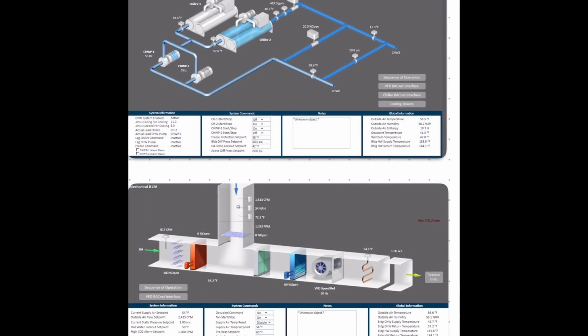Alright, so I put these 2 pictures together so you can have a better idea how the water cycle runs from the air handler to the chiller, or from the chiller to the air handler. You return from the air handler, goes here, then it goes to your pump first, and then your chiller, then it goes back to your air handler or building, however you want to call it, and then it goes to your coil in the air handler over here. That's where it comes in and it comes out. Then it goes back again, like I said, as you can see in the linings, to your chiller, and then it comes from your chiller to the air handler. This is just to give you a better picture on the water flow through the system. As you can see, it comes from the chiller, goes to the coil, then it goes back to the plant. Hopefully this helps you have a better picture on how the water runs through your system.